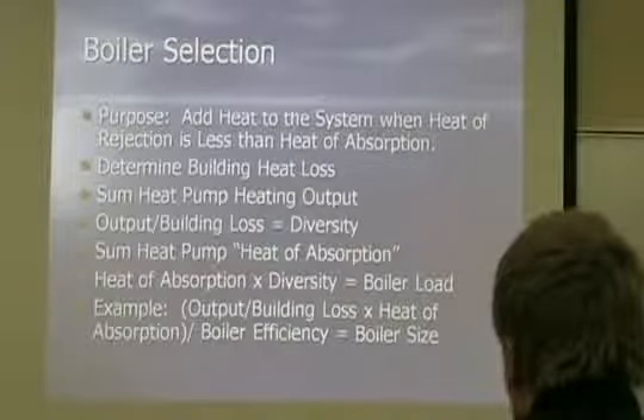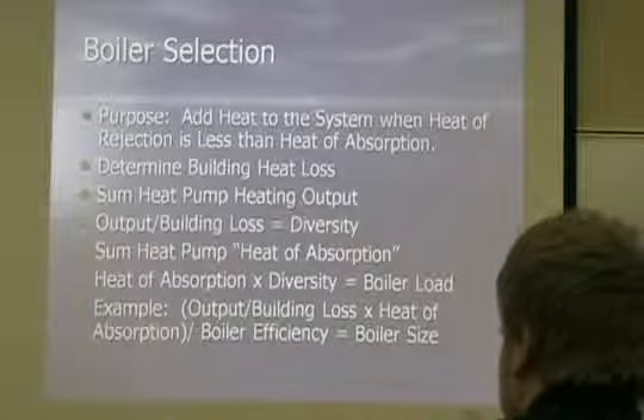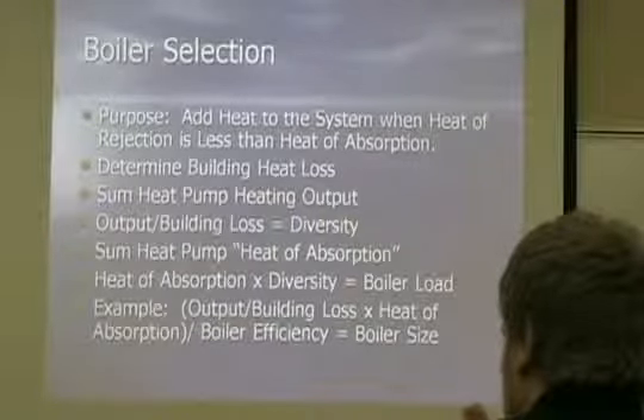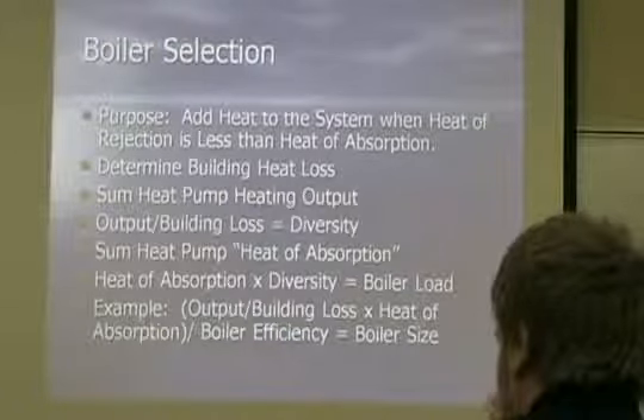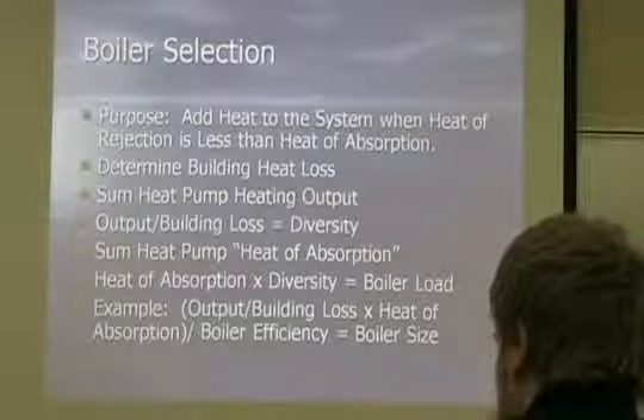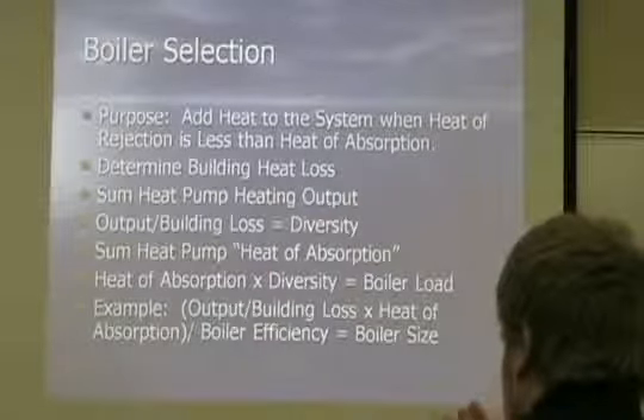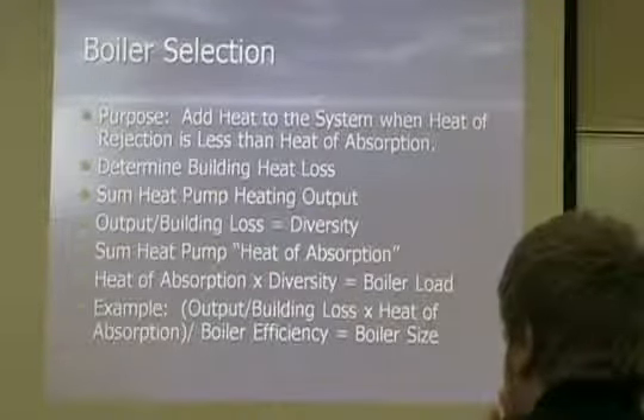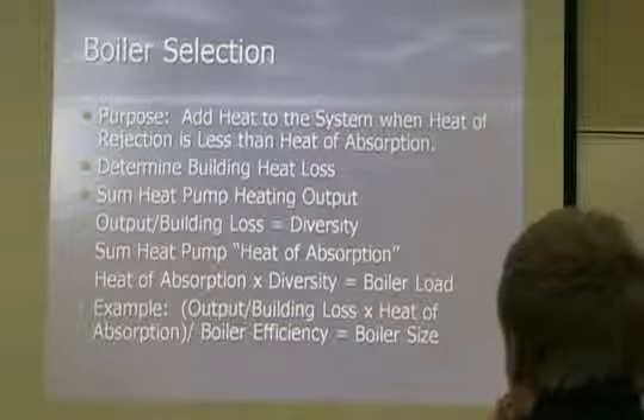Matter of fact, we have a little boiler in our building that's only about 100,000 BTUs. It heats this whole building because we're depending on the compressor heat actually being rejected to the loop, or enough absorption from the loop in the wintertime that we've got some simultaneous heating and cooling going on in the building.